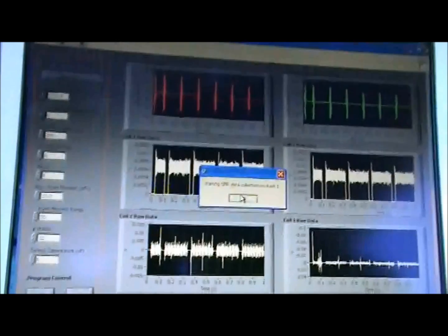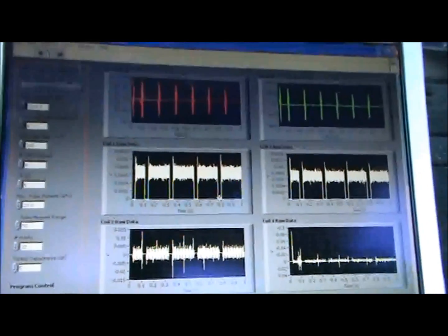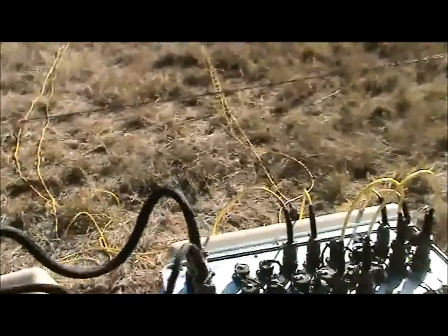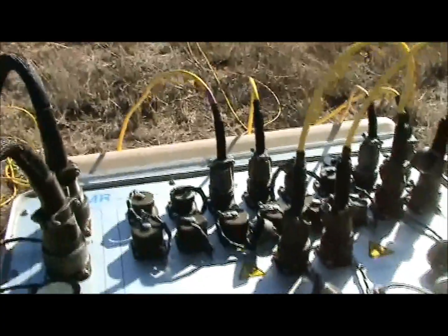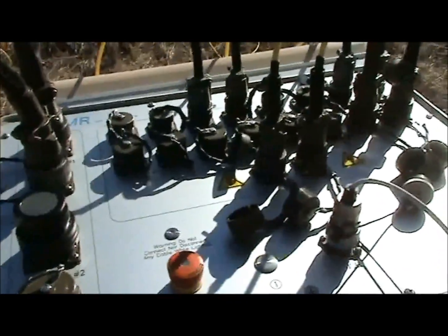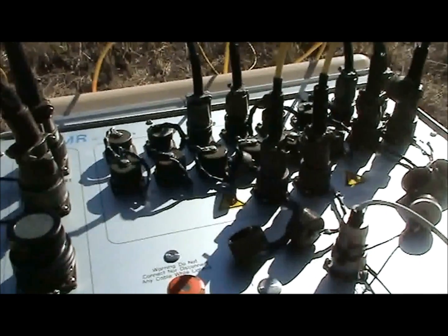TR of 6. The rest of these are good. Alright, so let's just start it up. So here we go. We're starting the 6. You can see we're going to actually get 6 echoes out of this sequence. So the CPMG sequence, you'll hear it when it goes off in a minute here. It's going to send off a very fast sequence of 7 pulses.